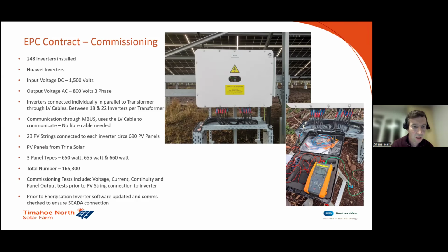Prior to energization, the commissioners will update the software on the inverter. They can do that centrally at the transformer center without going around to each inverter, and it'll send down the software updates to the inverters, and they'll check the SCADA communication back to the substation.